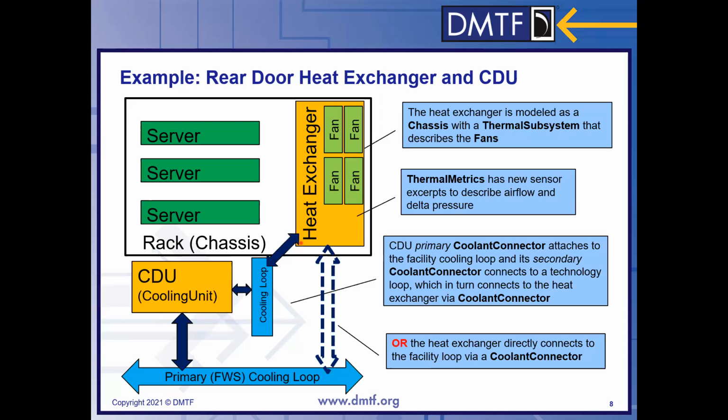So the fans are there; they all get monitored and controlled the same way that they would for a server chassis or anything else. There are some new sensors added to the ThermalMetrics resource underneath the thermal subsystem that allow the exposure of airflow and delta pressure sensors on the air side. So that's kind of how the heat exchanger works.